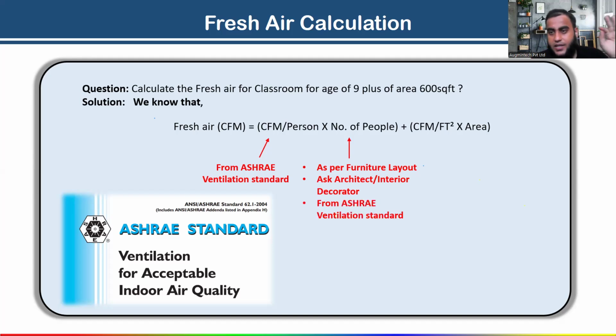In the last, we have one option from the ASHRAE ventilation standard. We can also calculate the number of people, the maximum number of people that will be there in this 600 square feet classroom area. That also I will explain to you, how to calculate. As per space, you can easily calculate. Same way, the CFM per square feet value you will get from the ASHRAE ventilation standard.